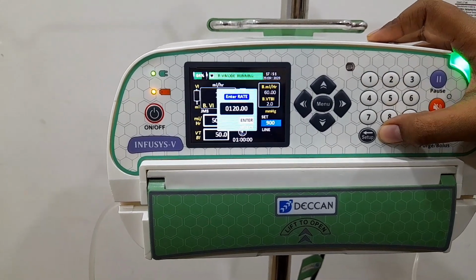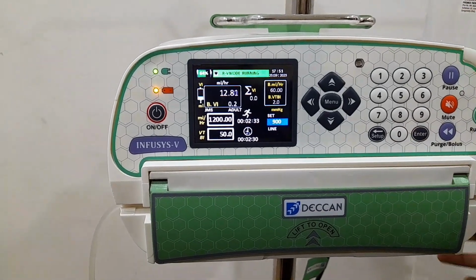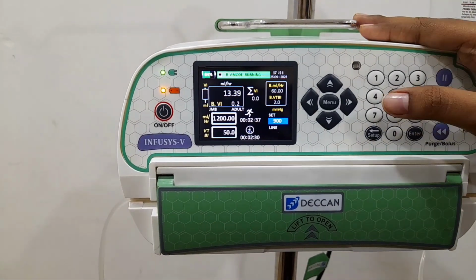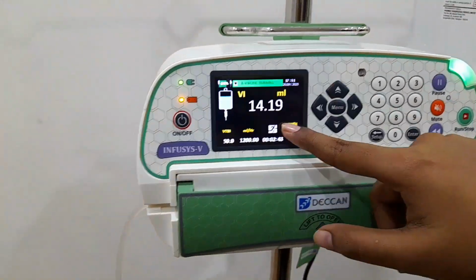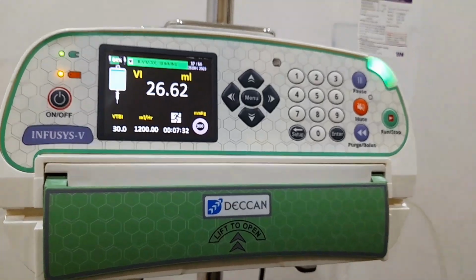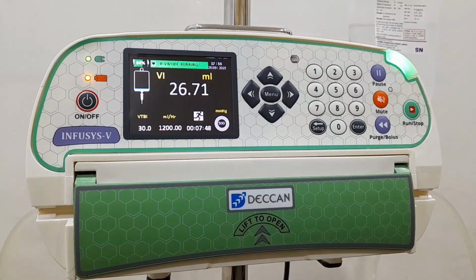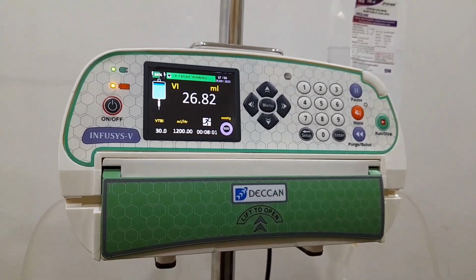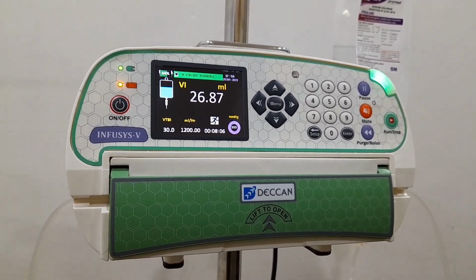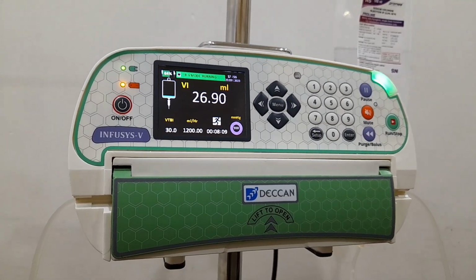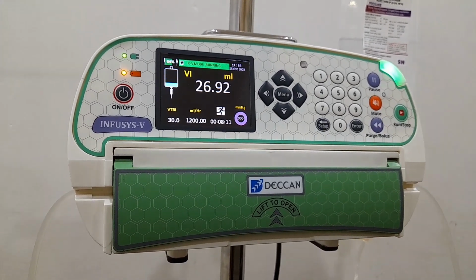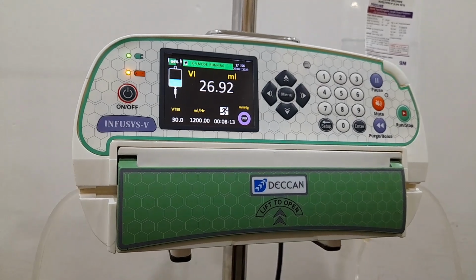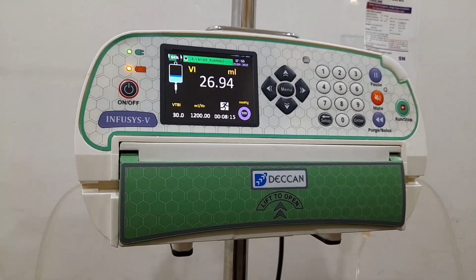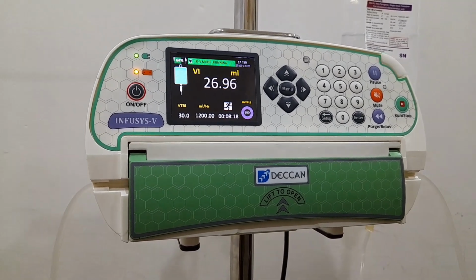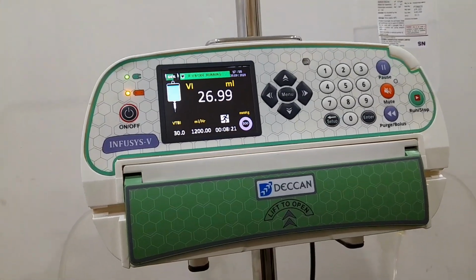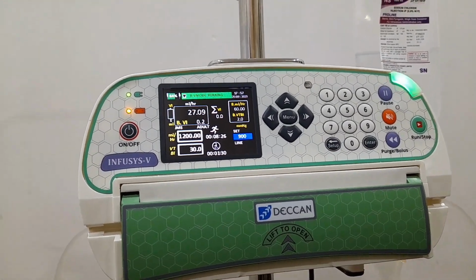So we can change the rate again to 1200 ml per hour. Wait until the infusion complete alarm occurs. In between, we have changed the volume to be infused to 30 ml instead of 50 ml, which is not shown in the video. Wait for the infusion completed alarm. When the infusion gets closer to reaching the target volume, the nearing volume limit pre-alarm occurs. Wait to watch the nearing volume limit pre-alarm. Here the nearing volume limit pre-alarm occurred.